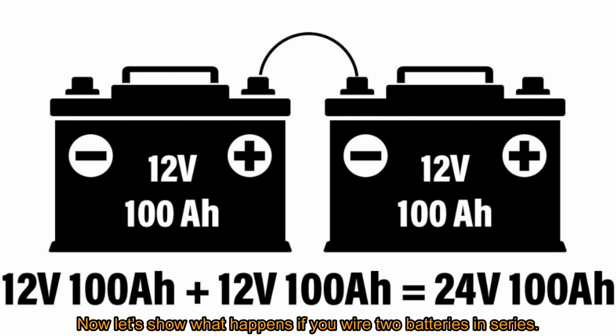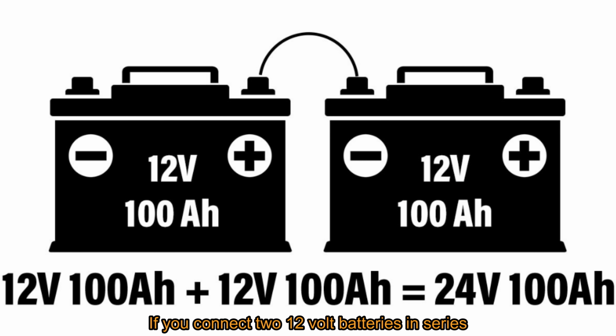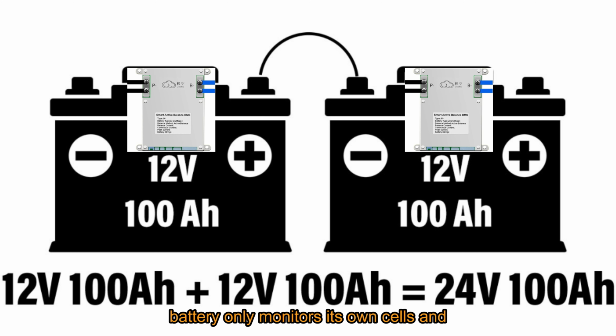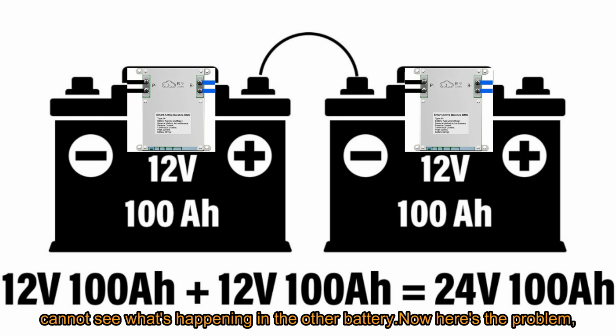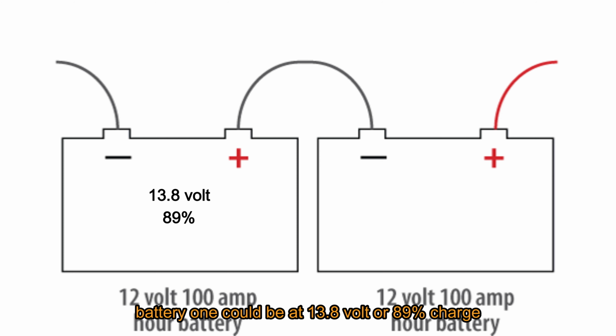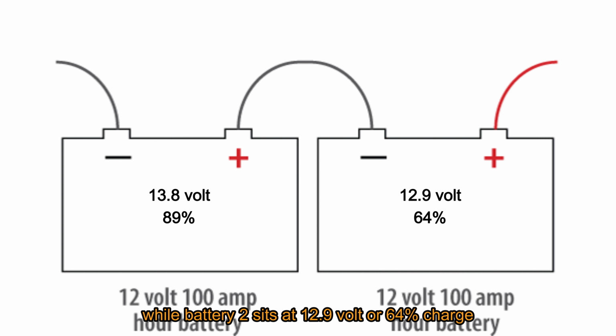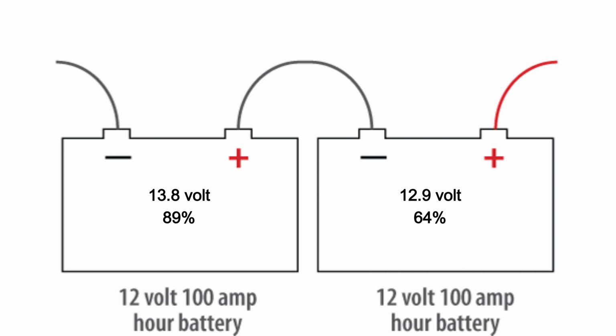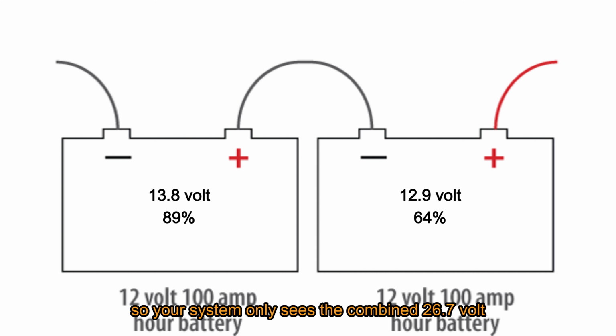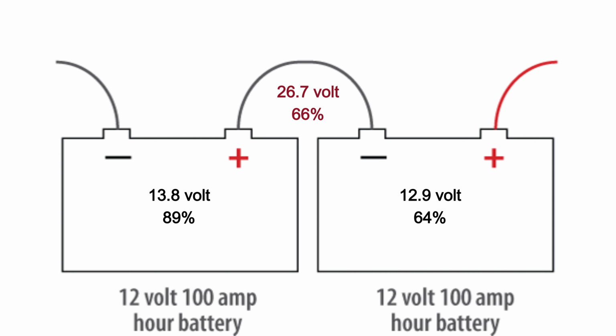Now let's show what happens if you wire two batteries in series. If you connect two 12-volt batteries in series for a 24-volt system, the BMS in each battery only monitors its own cells and cannot see what's happening in the other battery. Now here's the problem: battery 1 could be at 13.8 volt or 89% charge, while battery 2 sits at 12.9 volt or 64% charge. So your system only sees the combined 26.7 volt and thinks it's charged at 66%.